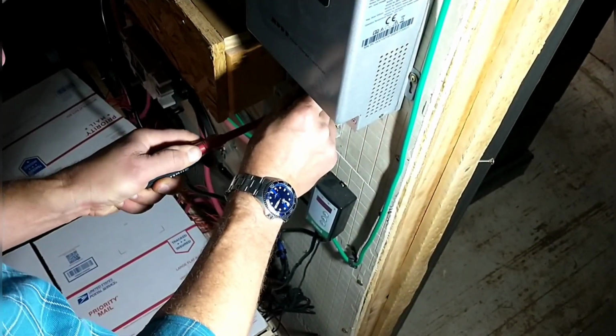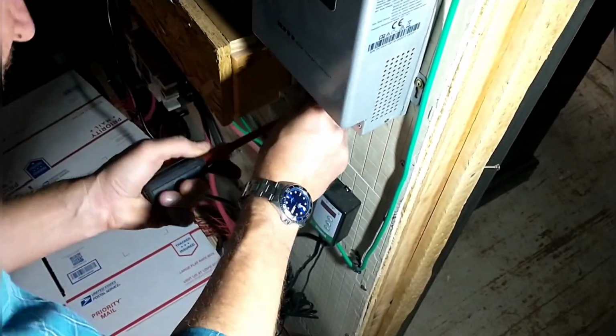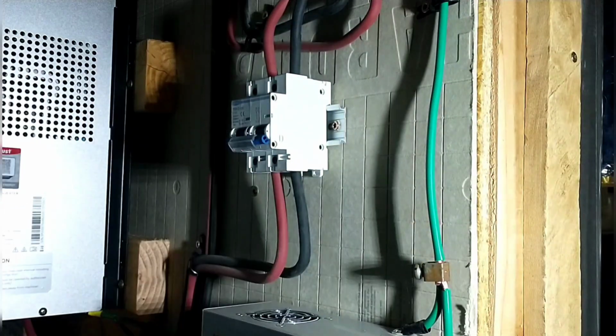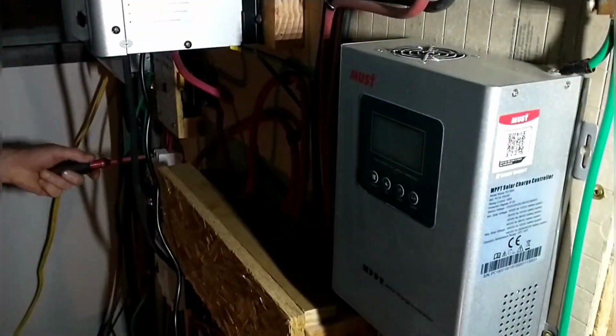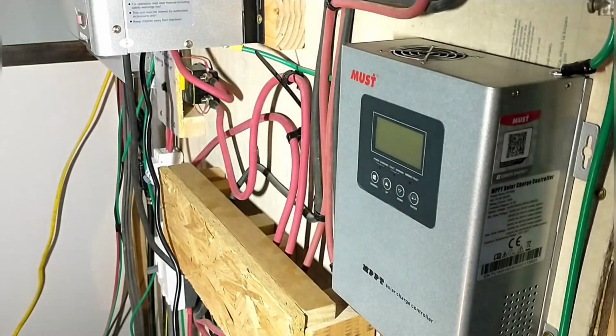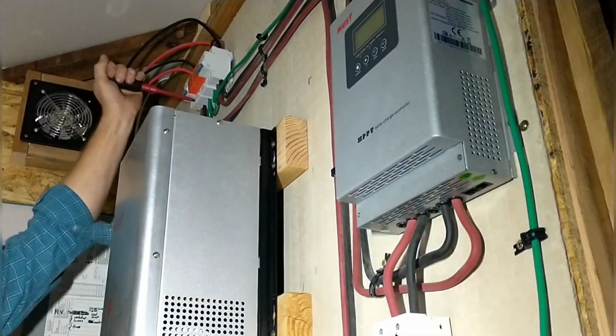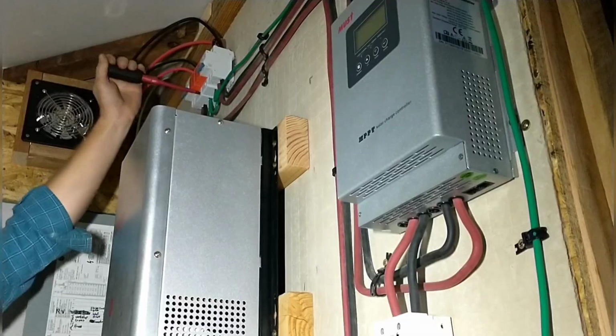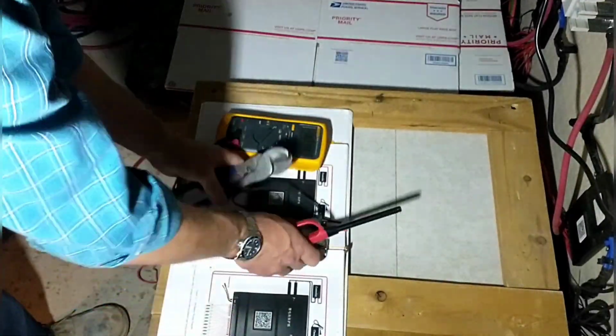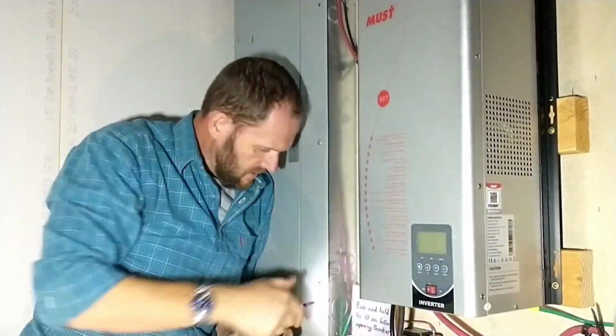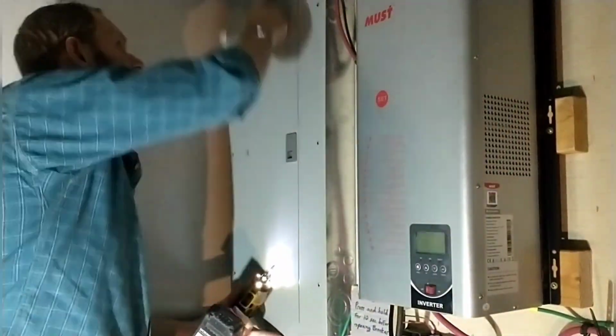We also checked the connections on the controllers, all the breakers, and other components in the system. I did find one loose connection on this particular breaker, one of the breakers below the controller, but that was the only one - everything else was still tight. I put the cover back on the battery as soon as I could, since those connections are always hot or energized, even when the system is down.